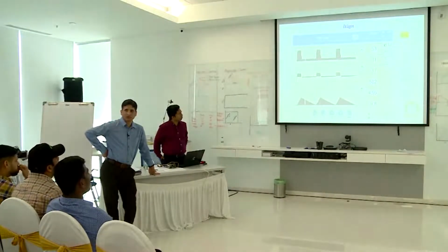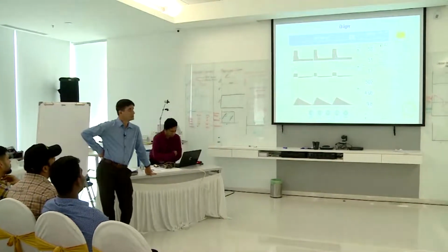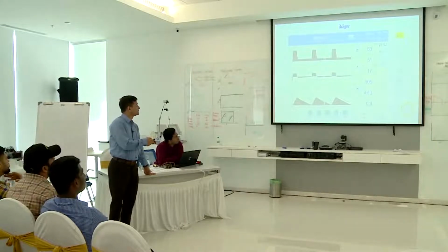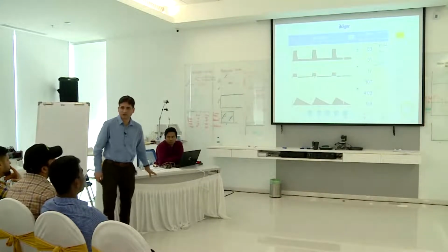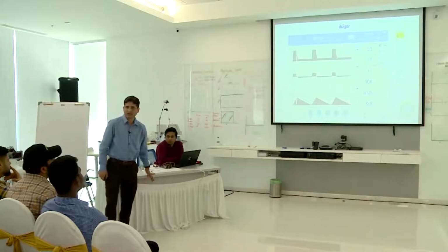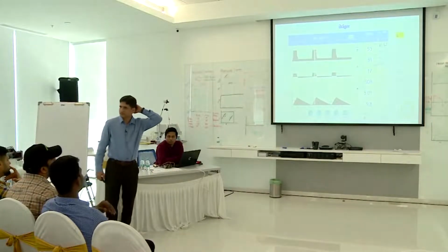And what is the problem here? See the peak pressure, it is going so high. If you see the value, it is 53. Normal peak pressure should be 20 to 22. Now it is going up to 53. So peak pressure is high. If the peak pressure is high, what could be the problem? In which cases does the peak pressure go high?